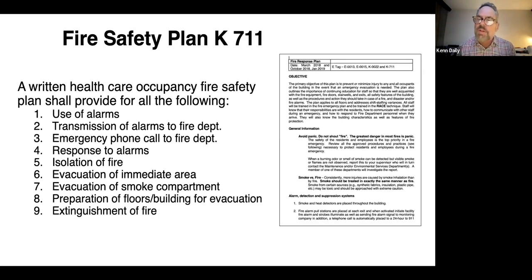Then what is the response to alarms? The most basic would be RACE or RACER: remove, alarm, contain and extinguish, or evacuate. Whatever I would tell you is really more RACE: remove, alarm, contain, and evacuate. Most of us don't have to worry about extinguish. You certainly can, but we are fully sprinkled, and so what that means to you and what you've trained your staff to do. And then isolation of fire, your compartmentalization, obviously the shutting of doors. And then you have the evacuation of the immediate area, which goes back to the R of RACE, removal of anybody in harm's way first. So then, of course, you have evacuation of the compartment where the fire is located.